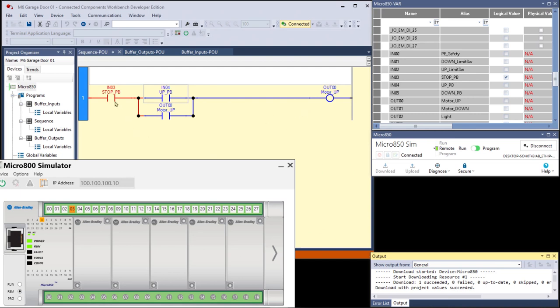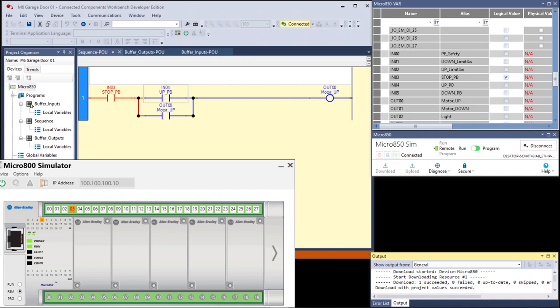So whenever we do a project with this type of logic, it's not going to run right unless you turn this on right at the beginning, because this is representing a normally closed push button, which would have continuity to the screw terminal. High voltage at the screw terminal. When I say high, I mean the high logic state, probably 24 volts DC goes through the opto isolator. And during the input scan, it updates that bit in memory, this bit right here, IO embedded DI3. And then when you run the buffer inputs program right here, scan it, it sets that bit high.